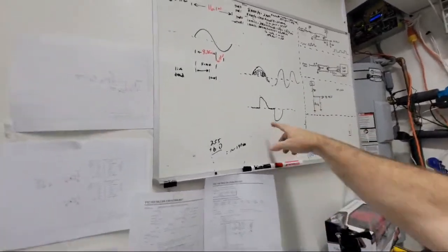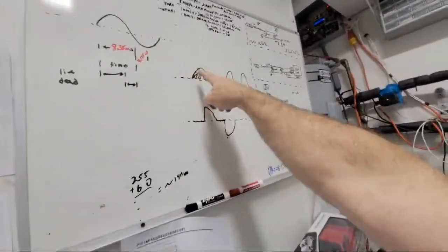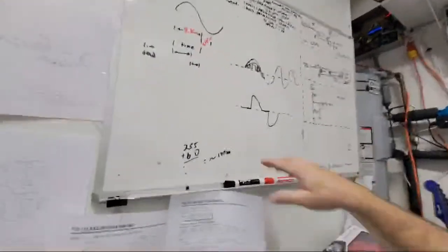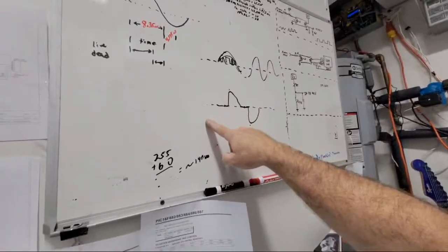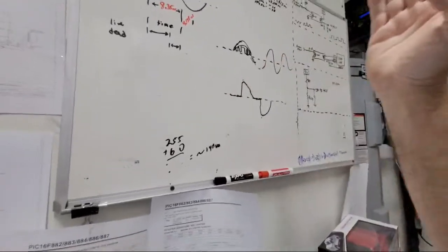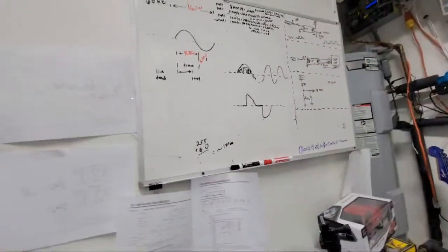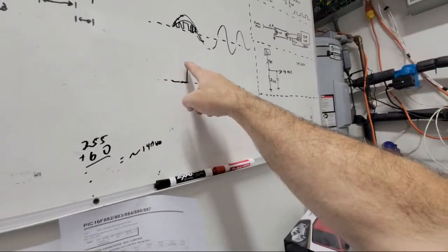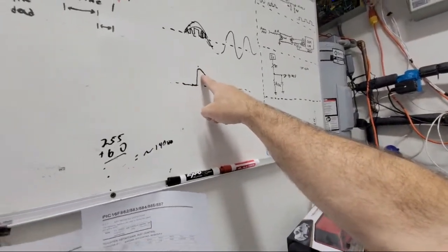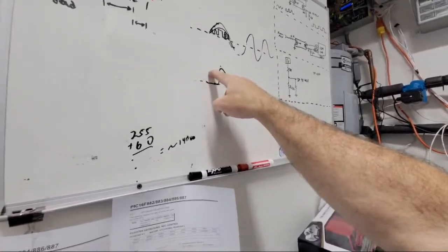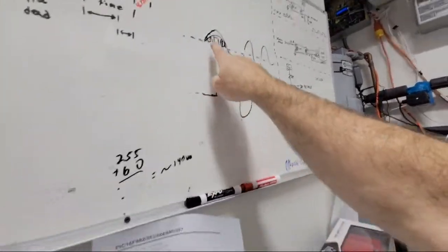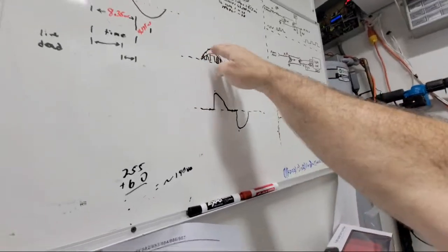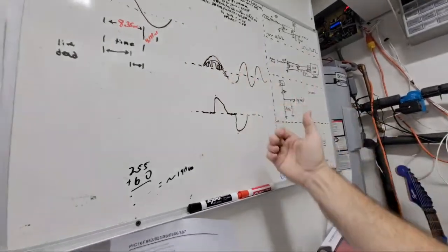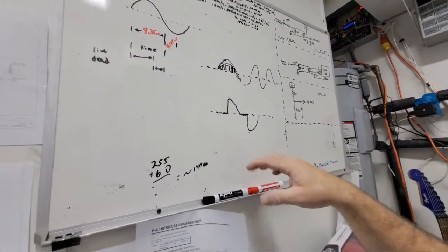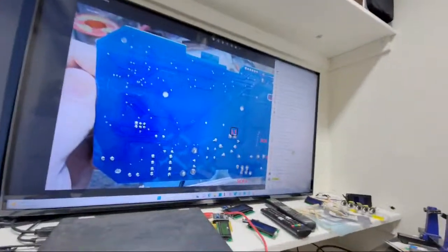You could do it electronically—have a microprocessor looking at the zero cross and counting so many milliseconds before it actually gates the SCR. That gives you the most control, because you could maybe gate it after the peak on its way down. You can't do that with just a voltage divider, because once you set a threshold, it has to cross that threshold on its way up—it can't skip it on the way up and then kick it on the way down. Not with just a voltage divider, but you can do that electronically.